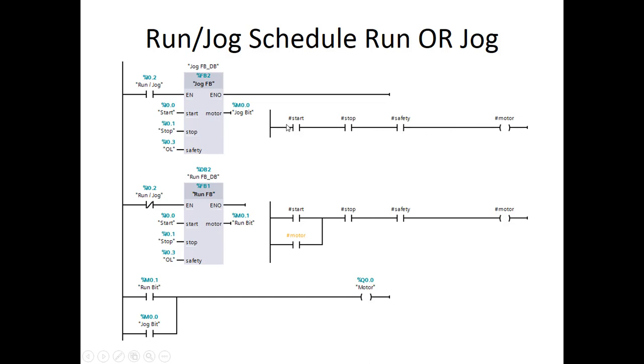If I hit start, all these things would be true and the jog bit would come on. Or if I scheduled this one and hit start, I would get memory and the run bit would come on. Instead of turning on a motor directly inside the subroutine, I took this bit or this bit and turned on a motor. So I ended up using the motor only once — the true output, the field device, is only in the program once. It makes it easier to troubleshoot, and it's obvious whether the PLC is telling us to turn on or turn off.